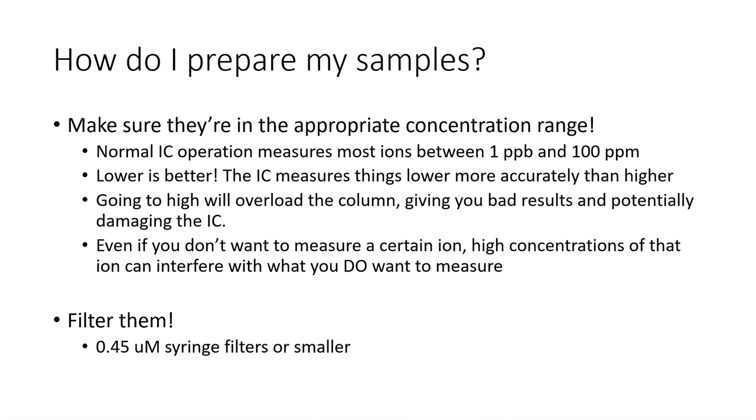In addition to that, going too high is going to overload the column, it'll give you bad results and potentially damage the IC. You might think you're saving yourself time by not diluting your samples, but when you get bad results and you have to dilute them anyways and you just wasted a week because the IC was running with all your samples that were too high concentration, you end up losing a bunch of time.